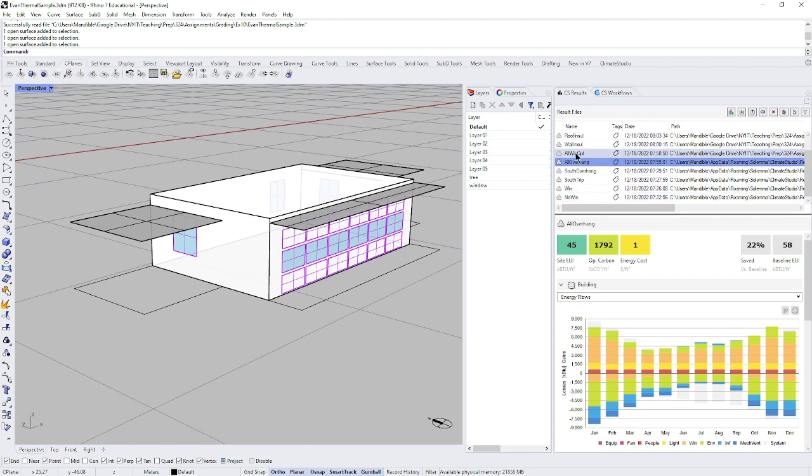The next thing I did was optimize all the windows. So I thought, well, okay, I don't need any solar heat gain on the east and west because I'm really just trying to prevent heat flow through, and I've already shaded them completely. I don't really want solar heat gain, so I just adjusted them, dropped the solar heat gain, and added more insulation, or lowered the U value.